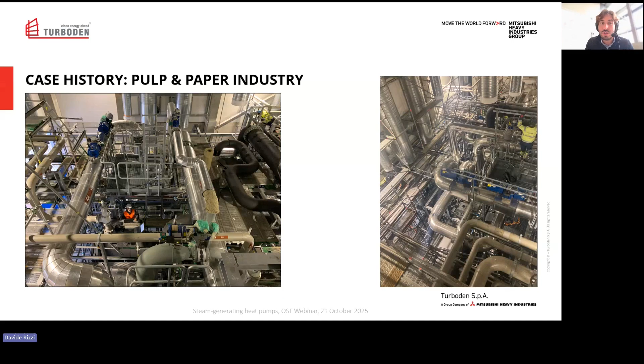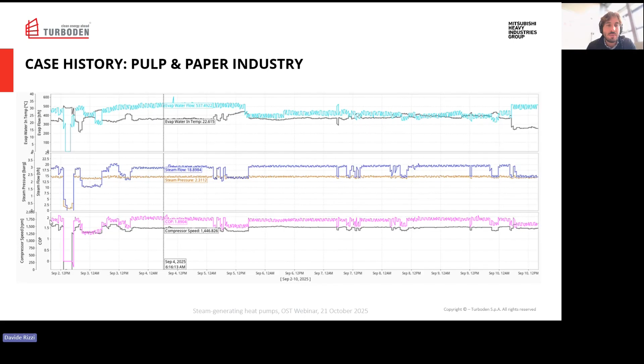Last but not least, you can have an overview - this is a screenshot of about a week and a bit more of operation, where you can see the evaporator water flow, the temperature of the evaporator, and the steam pressure. In this case, we were running at 18 tons per hour at 2.3 bar, and the COP - you can see that sometimes when the temperature of the evaporator drops, we have higher consumption, but at steady state, the COP is in the range of 2.